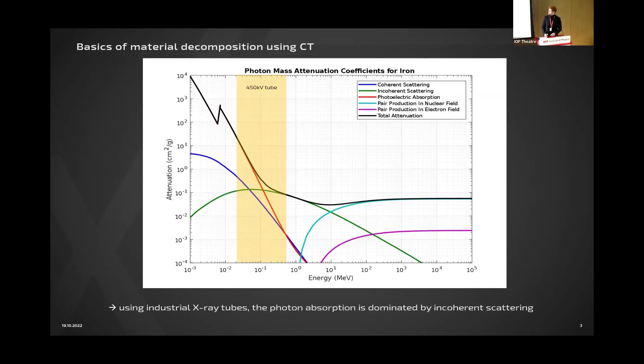You've already seen some kind of this plot. This is for iron, the attenuation. The most interesting part is this yellow area here. This is where a typical 450 kilovolt tube from our industrial use case is operating, and the peak photons, the most signal-dominating photons, are there.